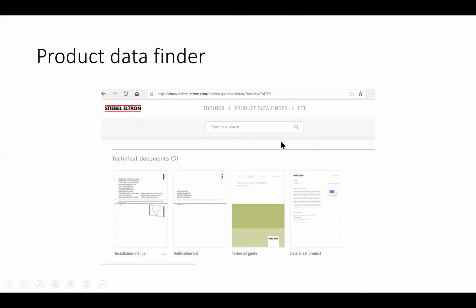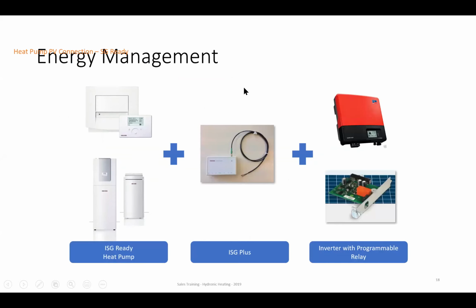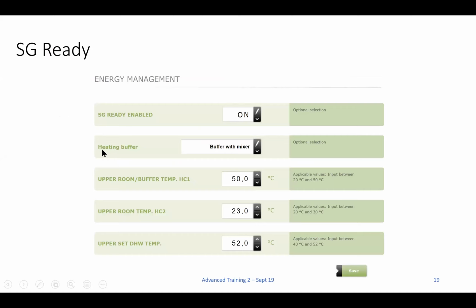Okay, so once you put it into energy management mode, what that allows us to do, through the ISG, is enable it to look at your buffer tank and any heating circuit that may be attached—remember, we can have up to another 4 mixed circuits. We can look at that room and say, all right, when we're producing all this excess solar PV, instead of the set point in the room being 22, let's make it 23, and instead of the domestic hot water temp being 50, let's make it 60, and the buffer tank as well. Remember, we encourage storage of hot water—to store hot water in a buffer tank is significantly cheaper than buying a new Powerwall. Powerwalls are 14 kilowatts or something like that; we can store considerably more energy at a fraction of the price when we're using buffer tanks.